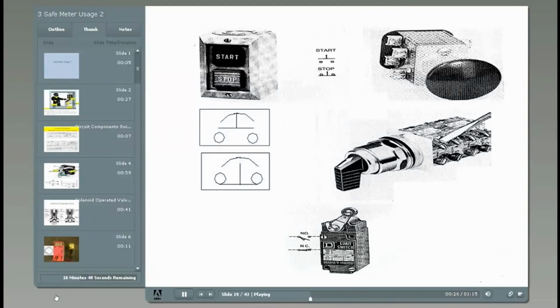A selector switch is on the center right. It could have 2 or 3 positions. Its operator could be maintained or spring-loaded. The selector switch can have several contact blocks, both NO and NC, that are stacked up behind it. When you turn the selector, there is a piston that goes down one side and will open and close the contact blocks on that side. On the other side is another piston that will open and close the contact blocks on that side.